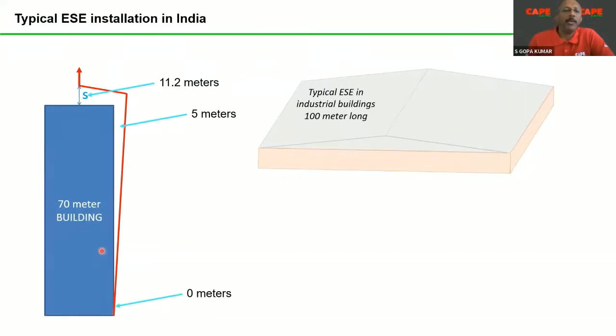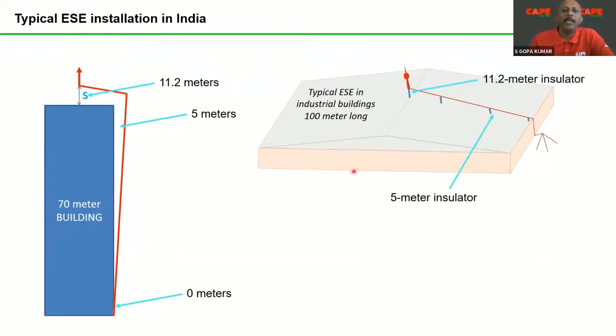In an industrial building hundreds of meters long, the distance is something like this. You have to have an insulator here at 11.2 meters, another insulator probably at 5 meters. So basically the air terminal and the down conductor have to be kept 11.2 meters away from the building. This 70 square mm wire insulation, 1.1 kV insulation, has nothing to do with this 11.2 meters insulation. 11.2 meters insulation is a large insulation. The spark-over voltage, the voltage created due to the surge impedance of the cable, is very high. This also means the lightning current flowing through the conductor to the down conductor can cause a flashover up to a distance of 11.2 meters.